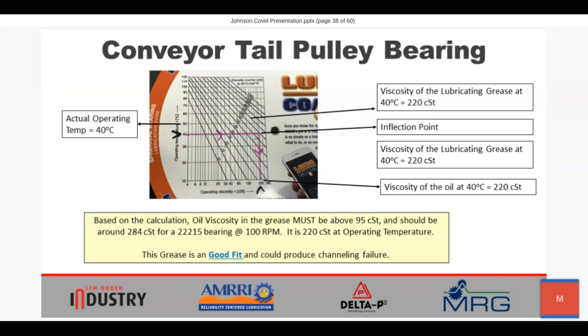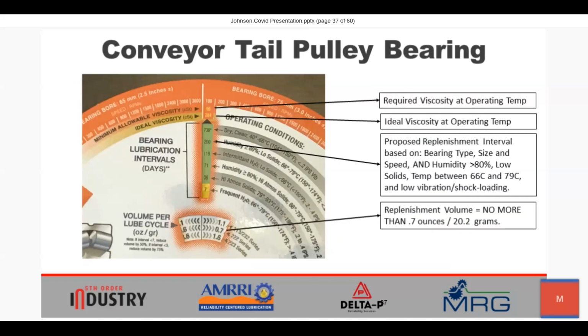We turn the calculation over to the back side. We see that if this bearing is operating at 40 degrees C and we're using a general purpose product, we actually have 220 centistoke for the product, where the bearing is looking for something between 95 and 284 centistoke. So then we find that the general purpose grease for this particular pillow block bearing is actually a very good fit. The product is the right fit.